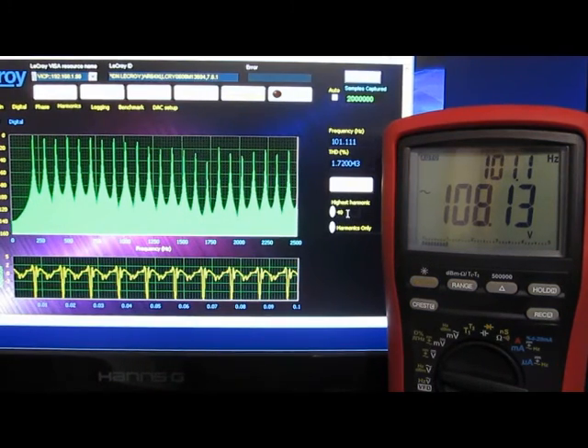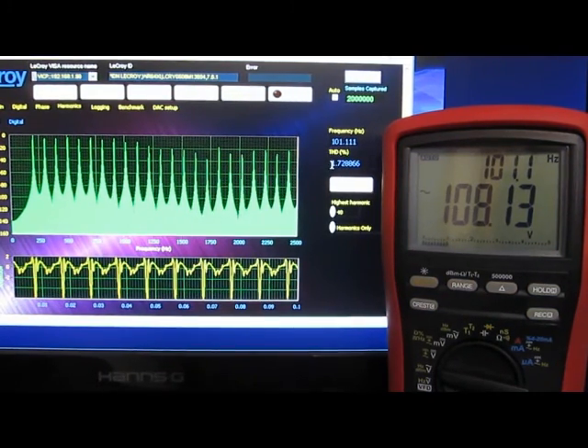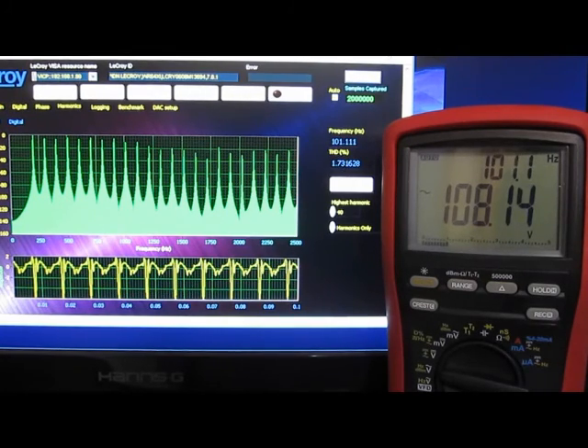Looking at the first 40 harmonics for the voltage waveform, we can calculate the total harmonic distortion as 1.7%.